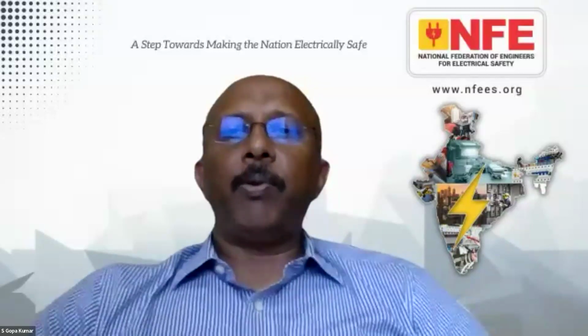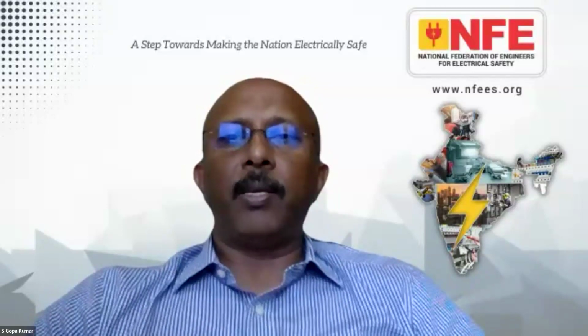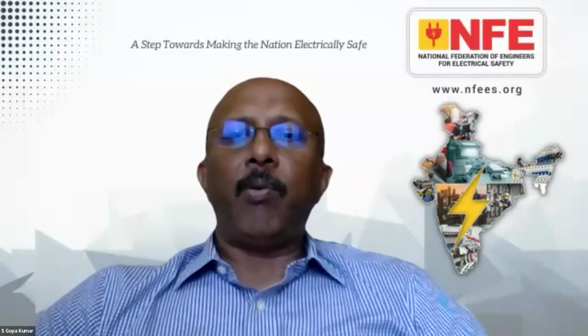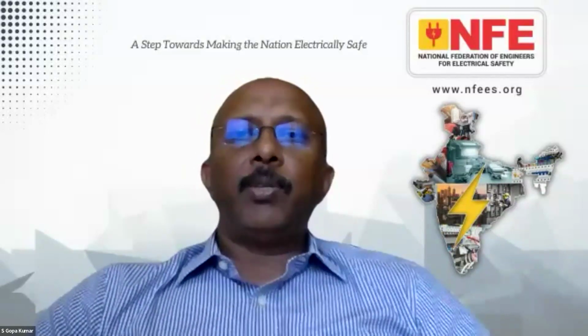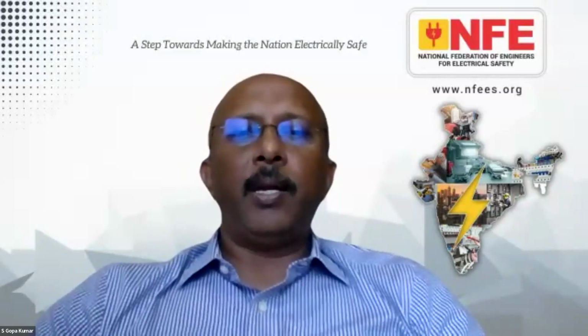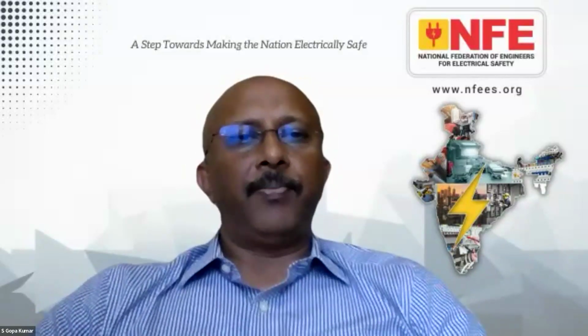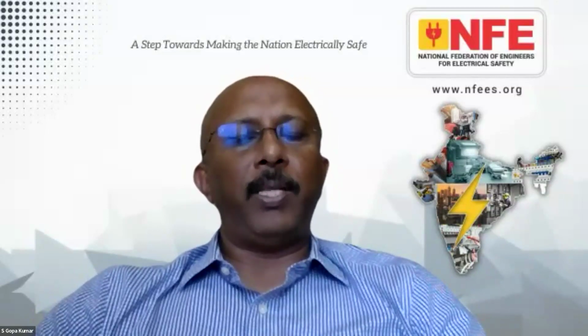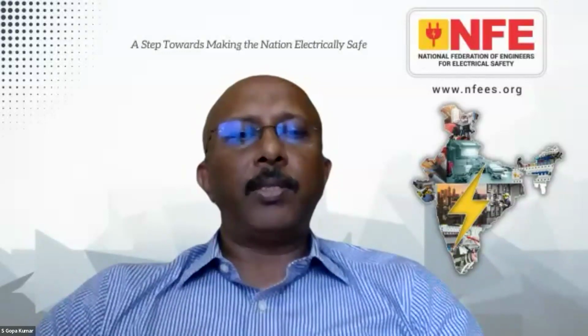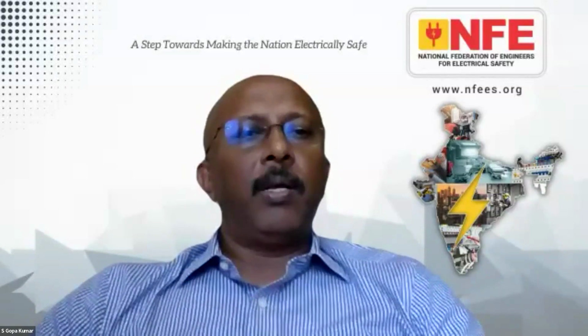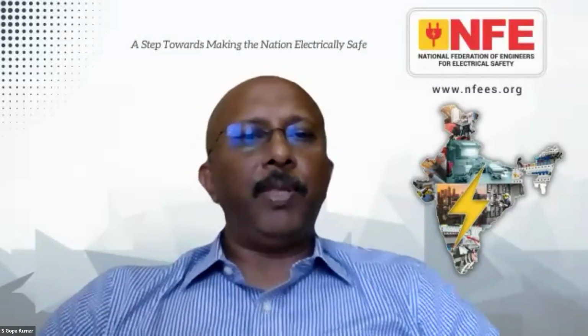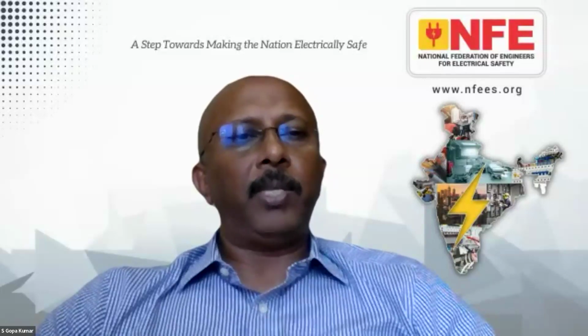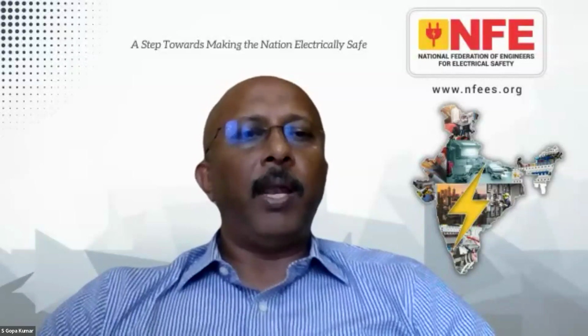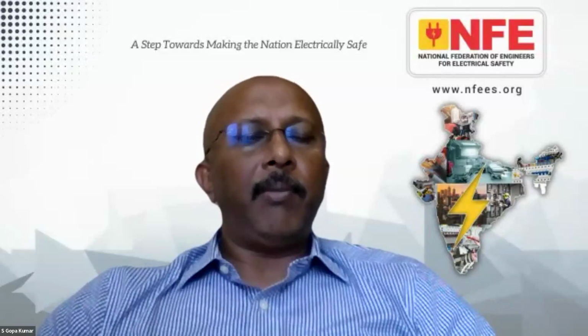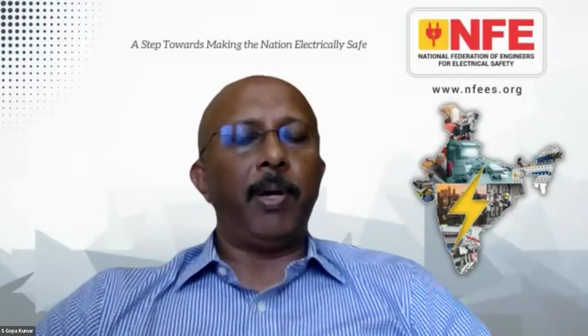Now we have a question from Mr. Subodh Bide. If there is a fault between line and neutral in the form of an arc instead of a solid contact, in that case, will arc resistance be added, or what will be the additional part of the loop impedance? Mr. Subodh, what the standard recommends testing is a fault of negligible impedance. Fault of negligible impedance means, for the purpose of testing, the impedance of the fault is considered as 0, because the condition is a live conductor directly in touch with a metallic exposed extraneous conductive part. That means the exposed extraneous conductive parts are at the potential of the live conductor. Then the disconnection time comes into the picture, and we ensure that the disconnection happens within that particular time.